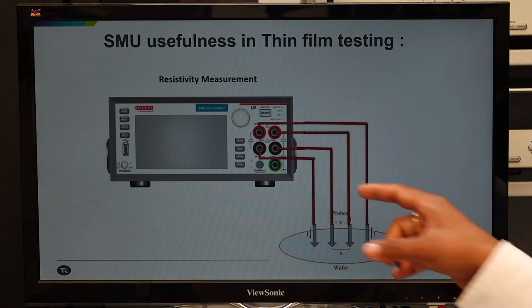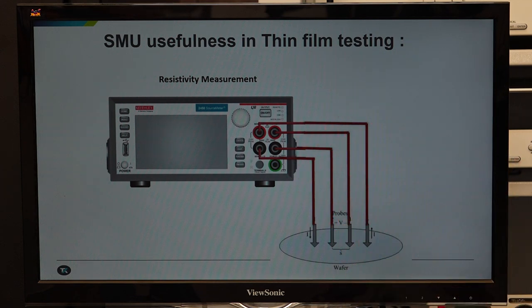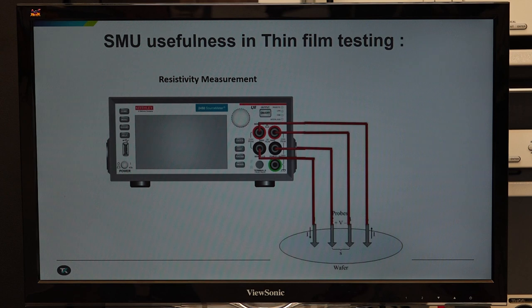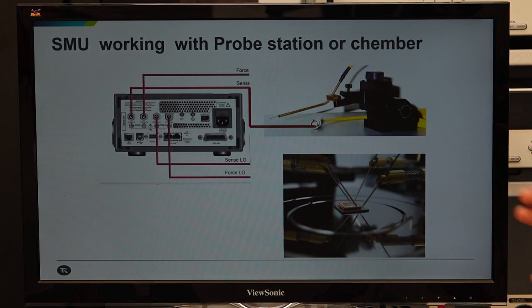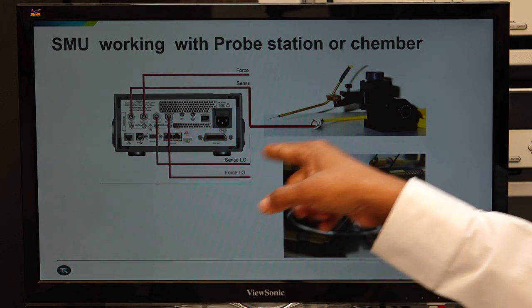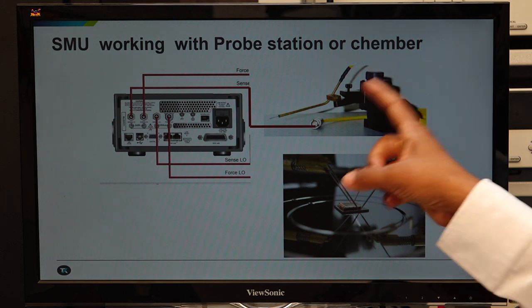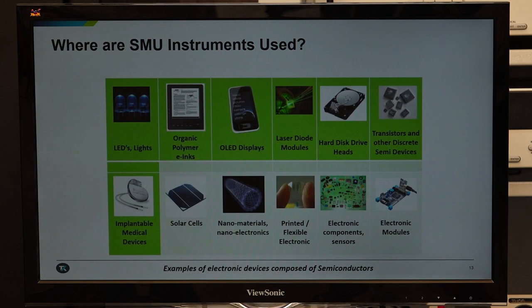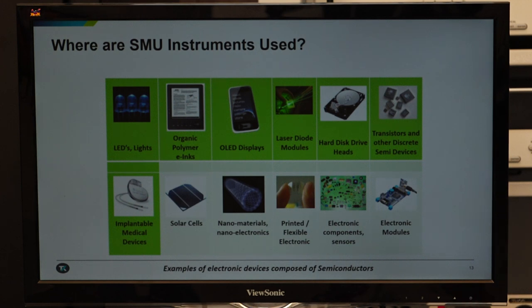When using SMU with systems like probe stations or environmental chambers, connections need to be made using BNC or triax. Most SMUs also support triax on the rear panel. SMU offers aspects from low current to very high current, low voltage to very high voltage, with built-in voltage source and current source. SMU is a very good candidate for characterizing various materials and devices.